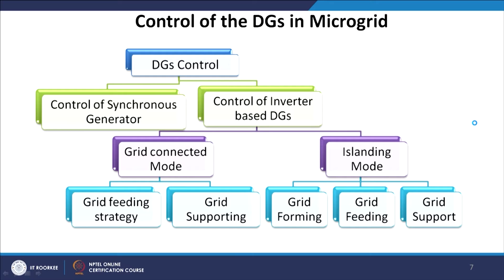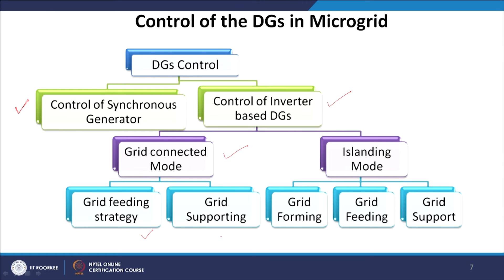Distributed generations within a microgrid and their control are classified as follows: first, control of synchronous generators; and then the major variety — control of inverter-based distributed generators. Synchronous generator-based control is classical, whereas inverter-based DG control is slightly different and will be the major focus of today's lecture. For inverter-based DGs, there are two types depending on the operation mode: grid-connected mode — which includes grid feed strategy and grid supporting strategy — and islanded mode.